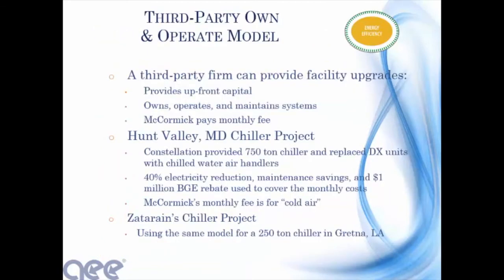The third-party own and operate model is an interesting way to get around some of the bigger projects if you want to save capital. You just saw an example of this with the CHP system that Chris can provide. We've had a similar financing model for the chiller plant I referenced earlier—we don't own that plant. A third party took out all the old air conditioning units, provided the new chiller plant and piping loop. They own the system, operate it, and maintain it. All we do is buy the cold air produced every month.